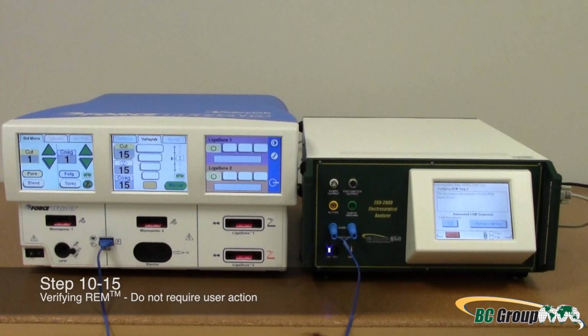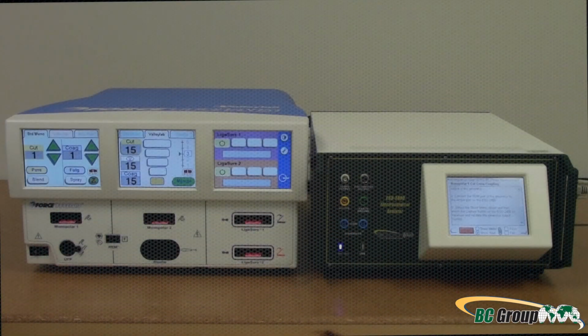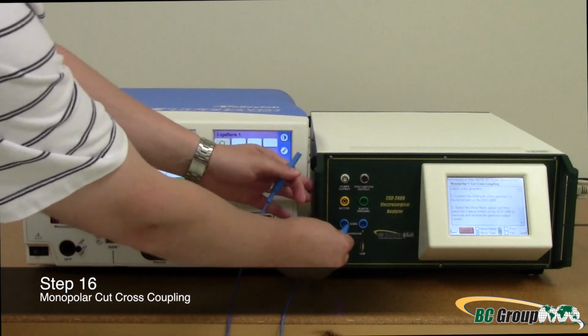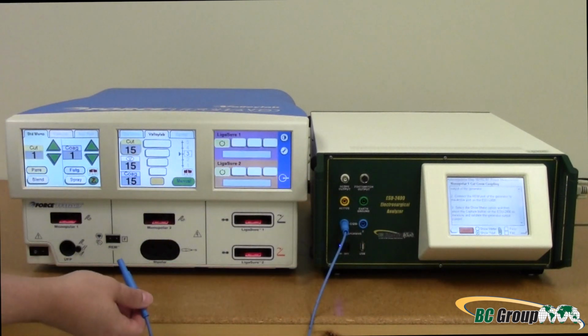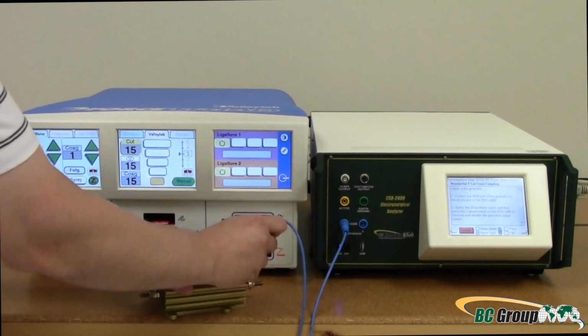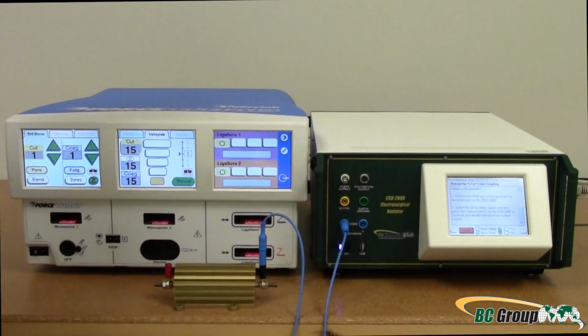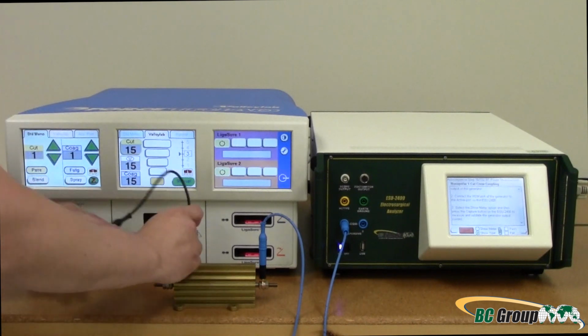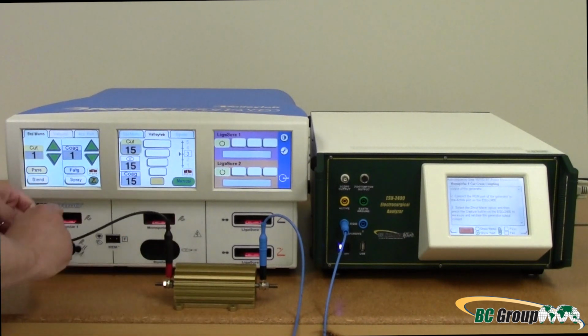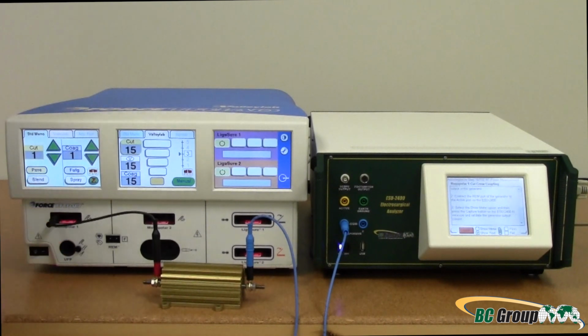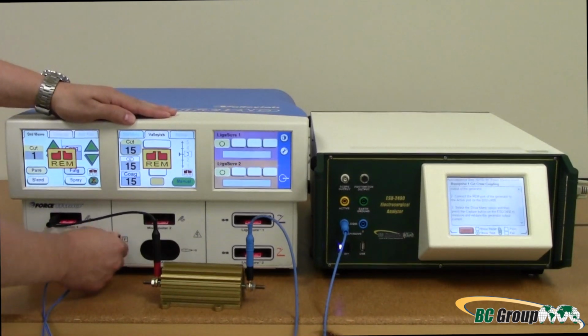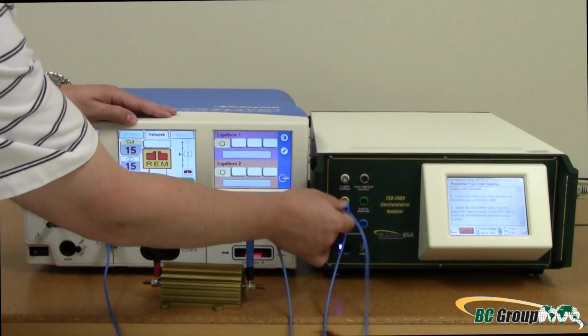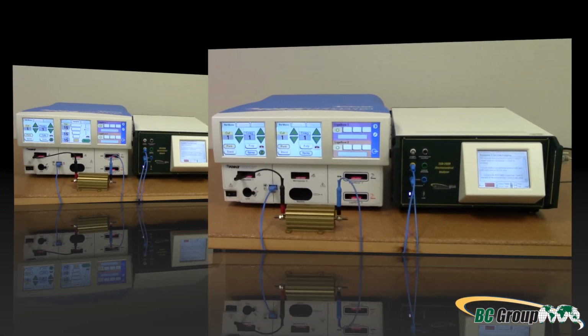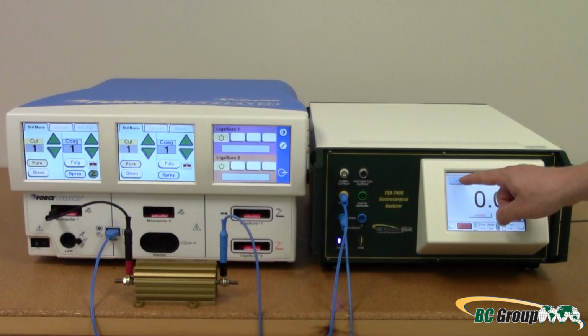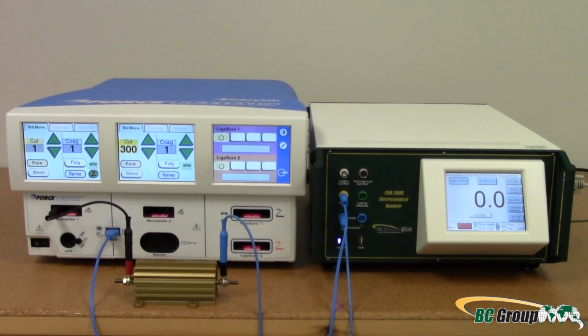Cross-coupling. Step 16. Monopolar 1, cut, cross-coupling. You will need a non-inductive external 200 ohm 250 watt resistor for this test. Connect the ESA-2000 dispersive 1 lead to one end of the external load. Connect the other end of the external load to the monopolar 1 output of the generator. Connect the REM port of the generator to the active port on the ESA-2000. On the ESA-2000, select the Show Meter button and then press Capture.